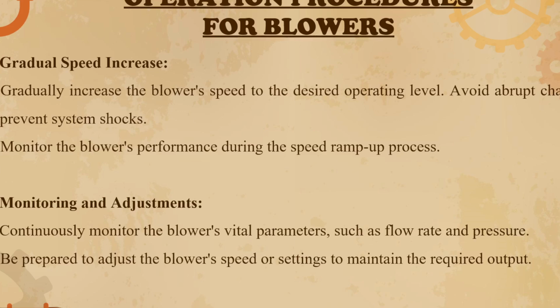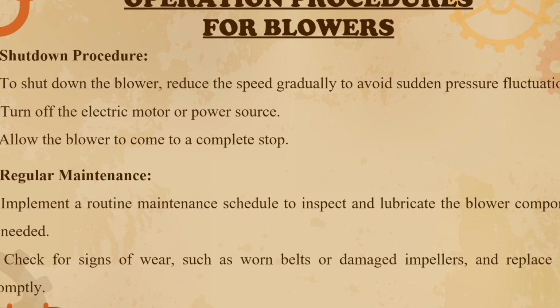Fourth procedure is the monitoring and adjustments. Continuously monitor the blower's vital parameters such as flow rate and pressure. Be prepared to adjust the blower speed or settings to maintain the required output. Fifth procedure is the shutdown procedure. To shut down the blower, reduce the speed gradually to avoid sudden pressure fluctuations. Then turn off the electric motor or power source. Then allow the blower to come to a complete stop.